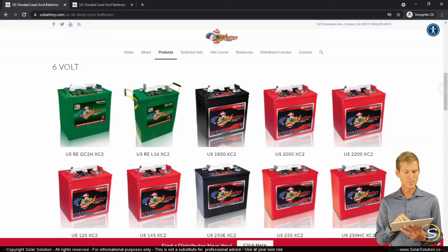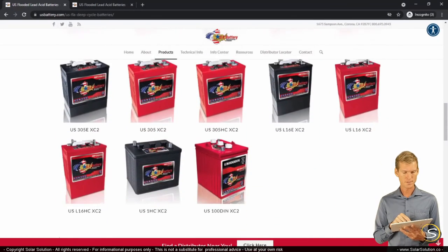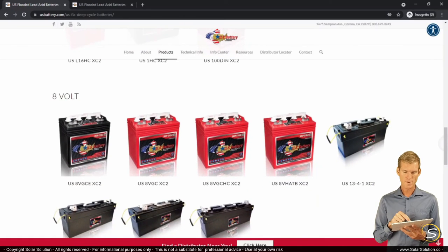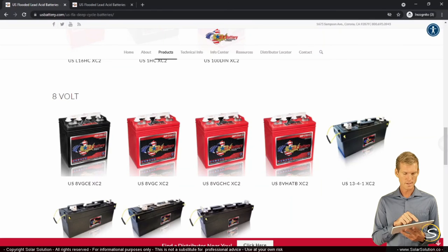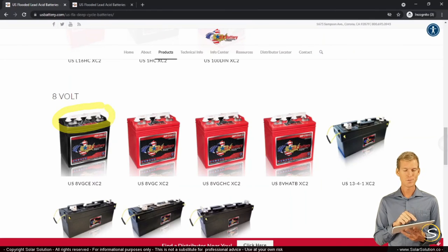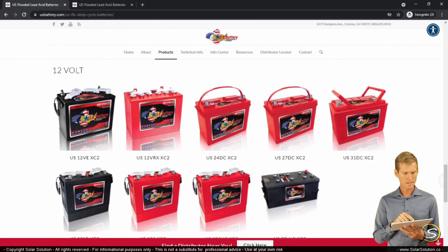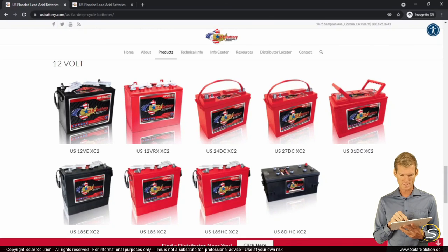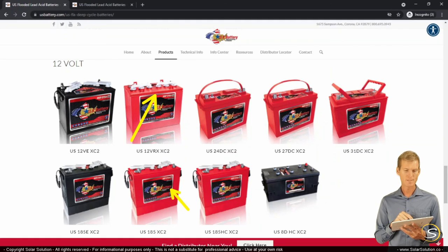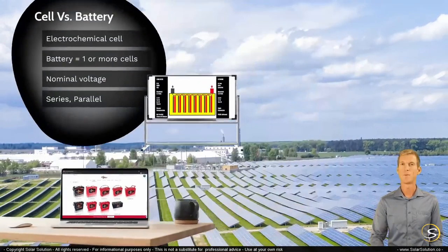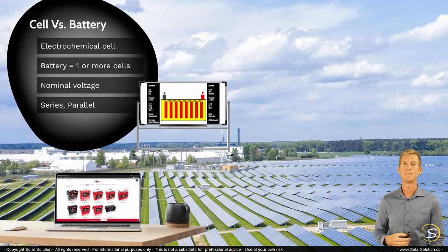Scrolling down further, this manufacturer also has 8-volt batteries — which is rather rare but can be a real advantage in certain situations. You can see these batteries have 4 caps, so 4 times 2 volts equals 8-volt nominal per battery — 4 cells each. Then we have the more standard conventional 12-volt truck batteries. Most of them show 2 rows of 3 filler caps — 6 caps total — meaning 6 cells inside at 2 volts each, giving a 12-volt nominal voltage.